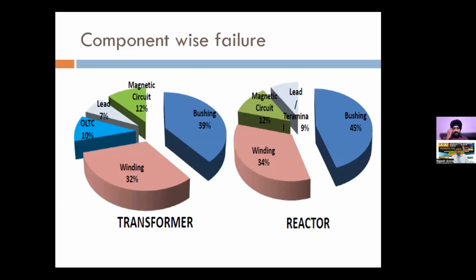When we try to detail component-wise failure, this data is based on the reliability survey of transformers. The transformer reliability survey says that a 1% failure rate occurs for a transformer across all utilities. So in power grid, we have a very low failure rate, around 0.32%. But overall, when you talk about all utilities worldwide, the failure rate is 1%. But when we look at the component-wise failure, in a transformer, around 39% of failures are due to bushings, 32% are due to winding failure, then 10% is due to OLTC, 12% is due to magnetic circuits. In power grid also, our failure rate is more or less on similar lines.